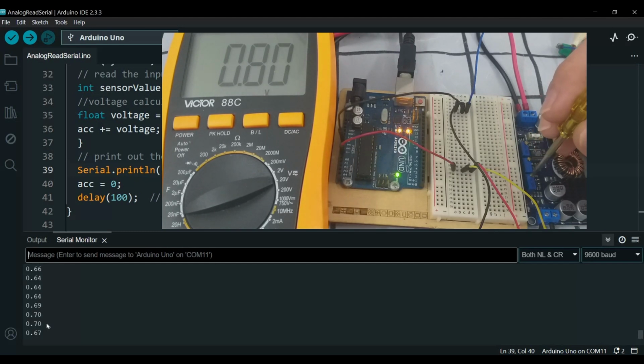If you want a 100% match, or higher accuracy, I can say we go to 2 points, but 1 point is more than enough. Let's say 0.8, and we go about 0.6, 0.7. If I go to, let's say, 1 volt, try to get it to 1 volt. Here we go, 1.05, 0.9, looks good. If I go for, let's say, 1.5 volt, almost there, 1.52, 1.4, okay, like 0.08 different, looks acceptable. 2.2 volt, 2.2 looks nice. 2.6, still 2.67 something, also acceptable. There we go. 3 volt, 3.17, 3.18, 3.2.